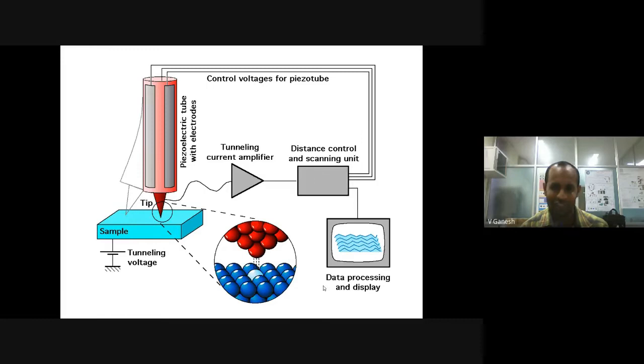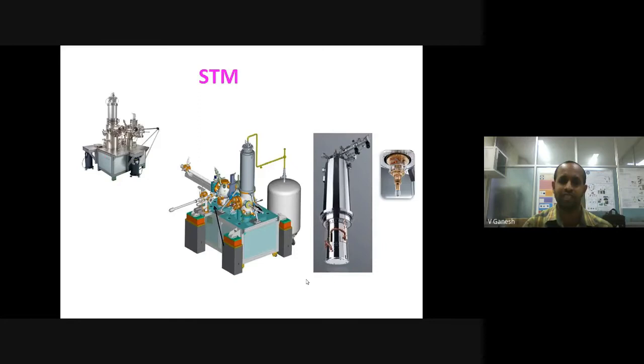For example, you cannot hold the pen perfectly still—it would vibrate on its own frequency. When I hold such a pen, it basically vibrates at the frequency at which I vibrate. That is called resonance frequency. So you need to dampen such a frequency, and that's why the scanning unit has been hung within the STM cell arrangement.